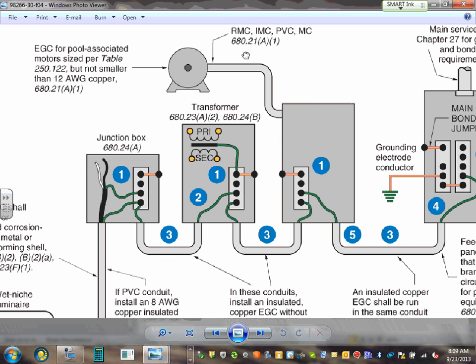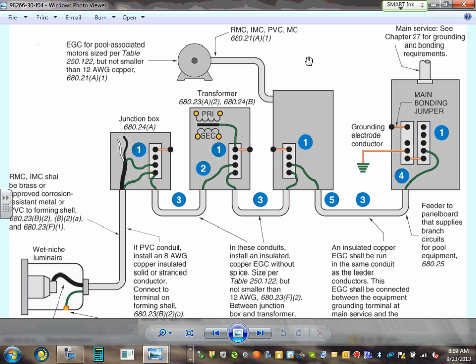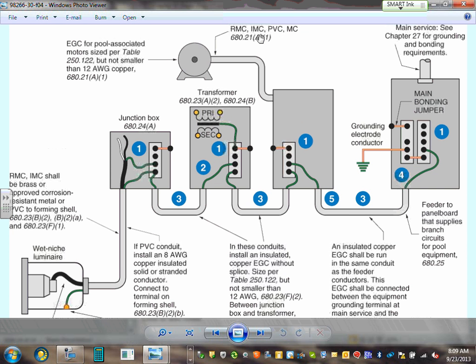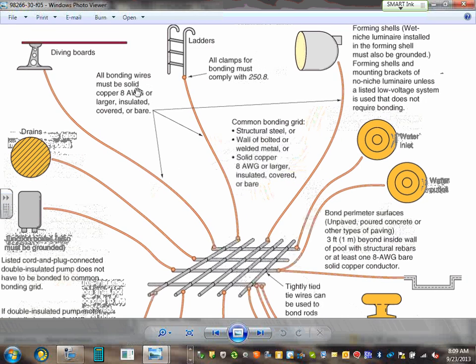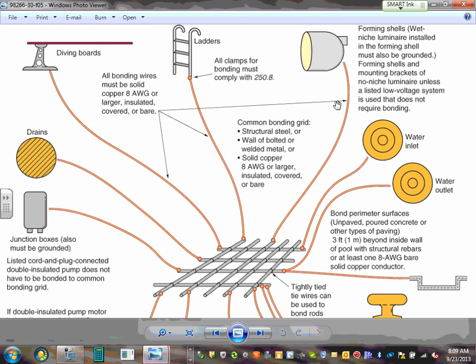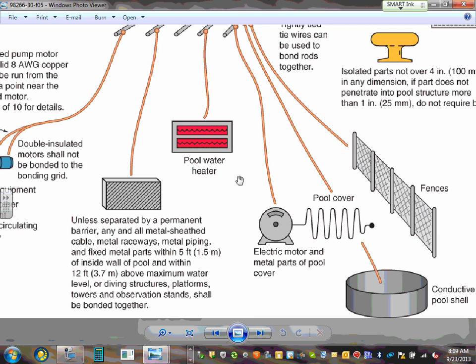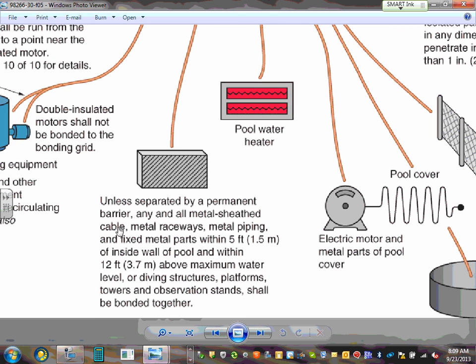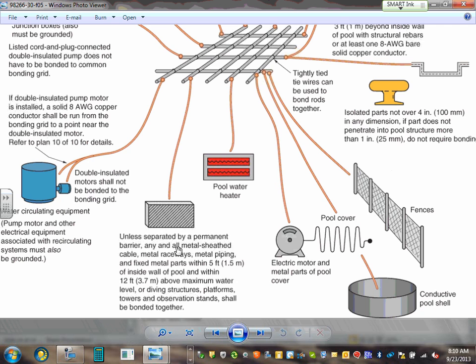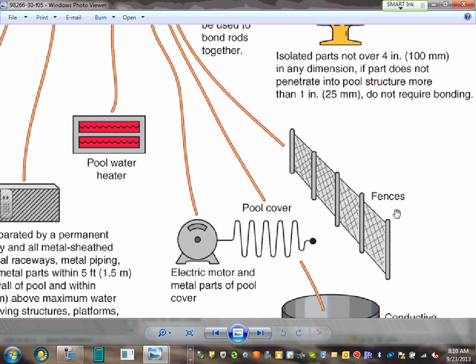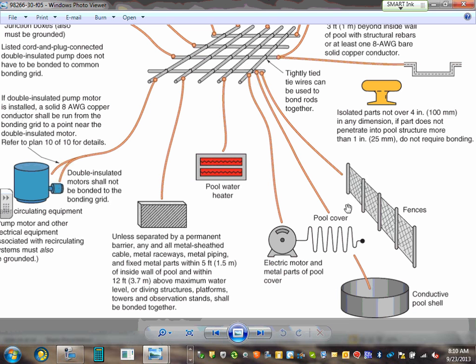So these are other regulations. An equipment grounding conductor is required. Here's the wiring method they use, guys, for pool-associated motors, with an equipment grounding conductor: you can use rigid, IMC, PVC, or MC. Don't forget the equipment grounding conductor for all these. Here's the grounding and bonding. Like I said, you can bond them all with number 8. Everything from the water inlet to the outlets, even the fences around the swimming pool. Look at this: unless separated by a permanent barrier, any and all metal within 5 feet of the inside wall of the pool, or within 12 feet above the maximum water level, shall be bonded. Same thing for the fences. I believe anything within 5 feet horizontal and 12 feet vertical, anything metallic around the swimming pool, must be bonded, including fences and so forth.